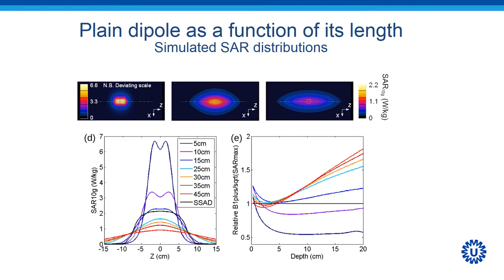If you take a look at the SAR distribution, you can see the same thing happening. For short antennas, the SAR levels at the surface are the highest, while for longer antennas, the SAR levels are much lower. If you take a look at the ratio of B1 plus over the maximum SAR, which is indicated in the second diagram relative to the single-sided adapted dipole antenna, we can see that for a depth of 10 cm, much longer antennas of 30 cm or even longer have the best performance.